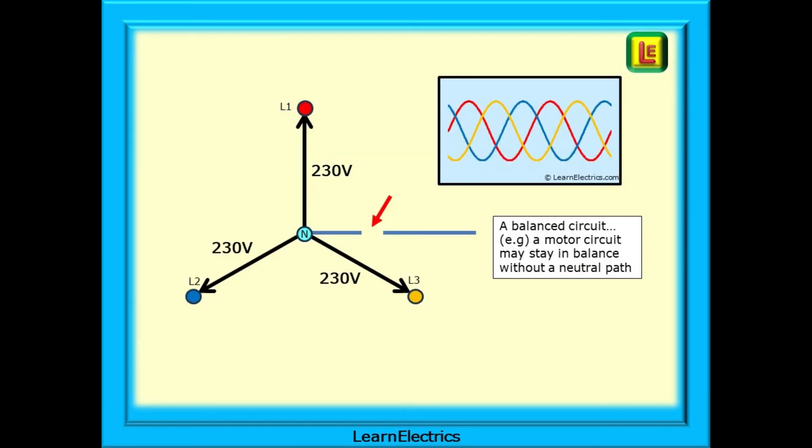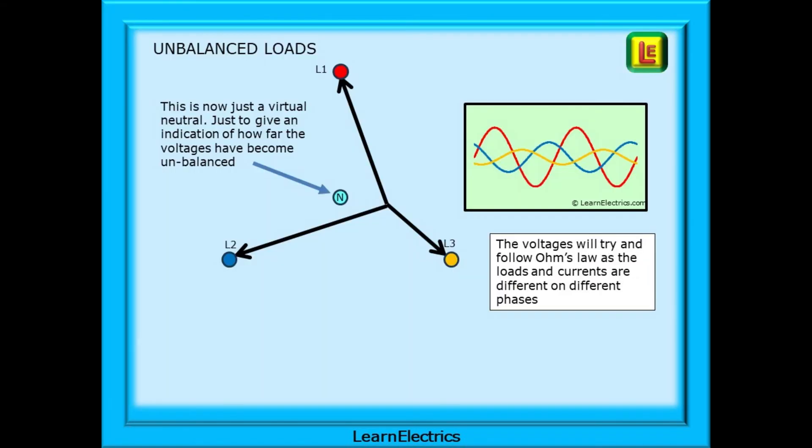Why has this happened? Why are the voltages suddenly at 400 volts? In a perfectly balanced circuit, they will stay at 230 volts. They didn't need the neutral before, they don't need neutral now. A balanced motor circuit will stay in balance without a neutral path.